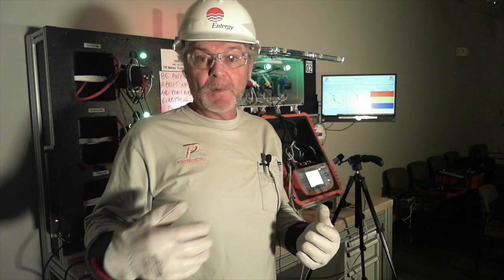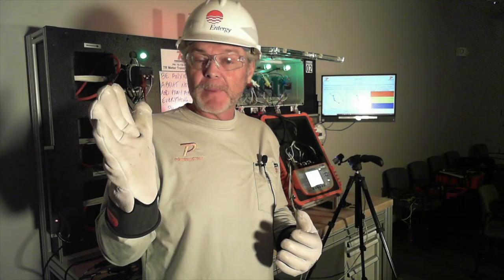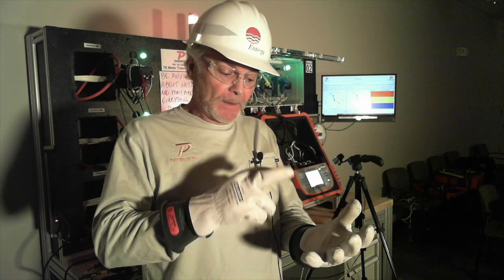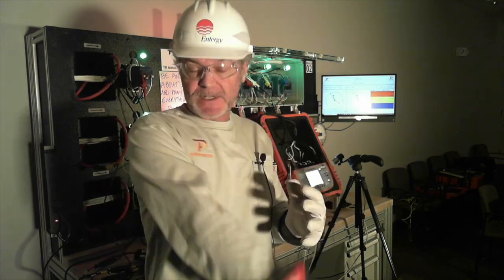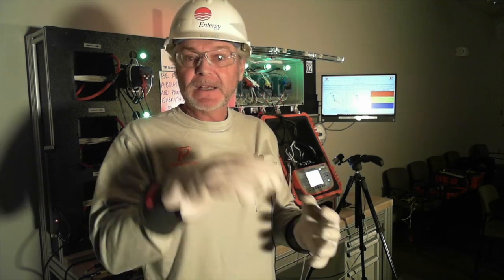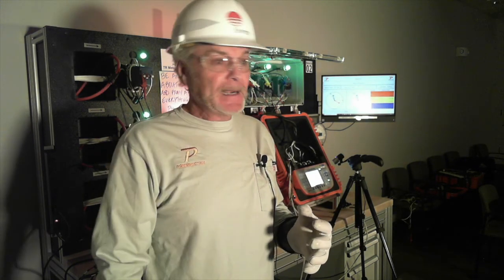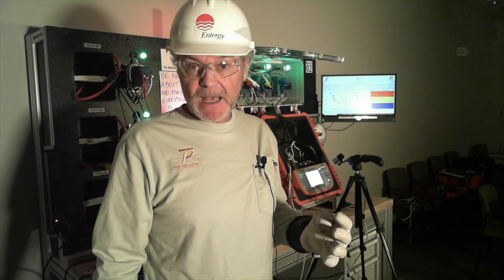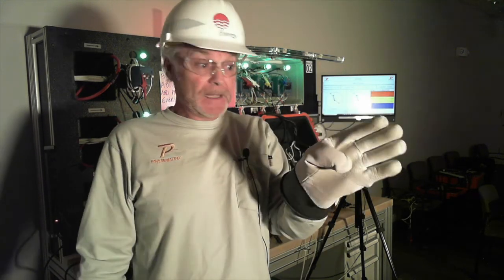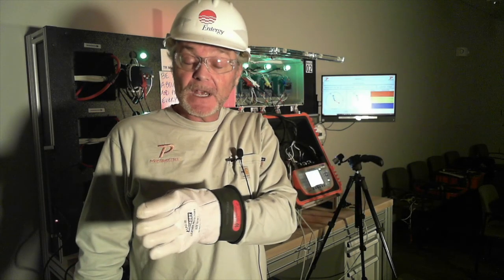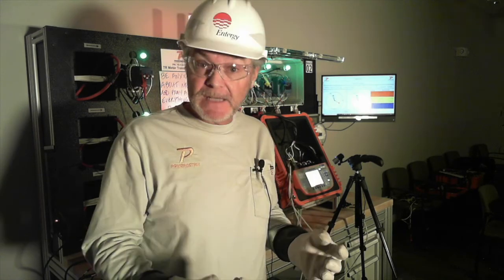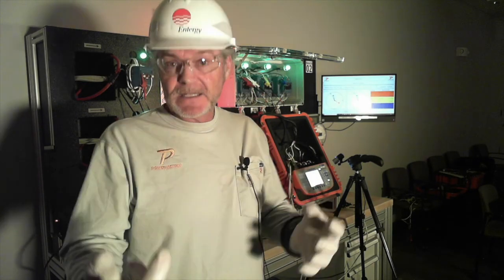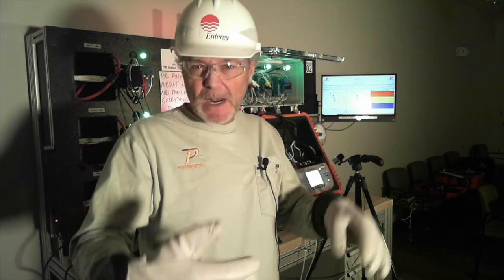That's acceptable. But if I start getting the higher amount of burden on there, CTs don't like resistance and they don't like heat. If you put too much resistance on them, accuracy goes in the toilet. If I get them too hot, the accuracy goes in the toilet. And 99.9999% of the time, we lose, right? So this will allow you to see the burden on each of the 3 phases, and you can actually do something about it. Step 1 in the process, tighten everything down. Step 2, retest it. You see what I mean? You can actually set up a process, all right?